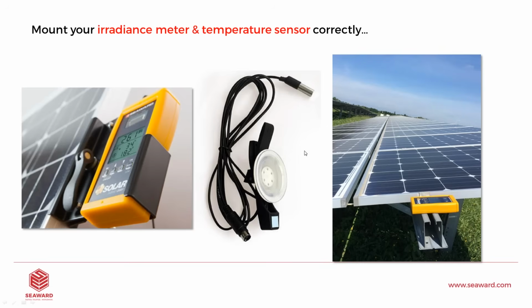It's also vital that we mount our irradiance meter correctly. Working in the industry and with the Seaward equipment for quite a while now, I've found that some people do not mount the irradiance meter correctly. They will lay it on the floor, they won't connect it at all, or they will put it on top of the panels that they're testing, and again, that's going to cause a big shading and hot spot. So I would recommend using a mounting bracket to mount your irradiance meter. And this goes the same for the temperature probe.